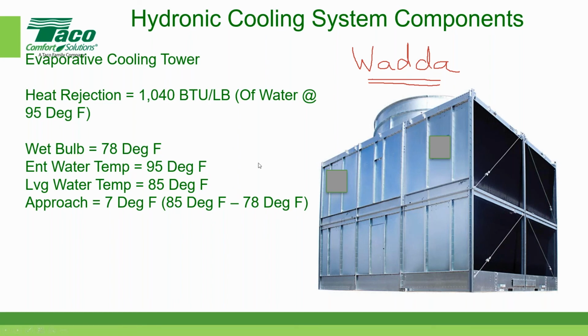If you want a shorter approach, say a 5-degree approach, you can certainly order that from your cooling tower rep, which would be a Taco rep. Most of our Taco reps have a cooling tower line. And if you want a closer approach temperature to make the chiller a little bit more efficient, you're going to have to buy a physically larger tower and perhaps even a higher airflow, so a little more horsepower.